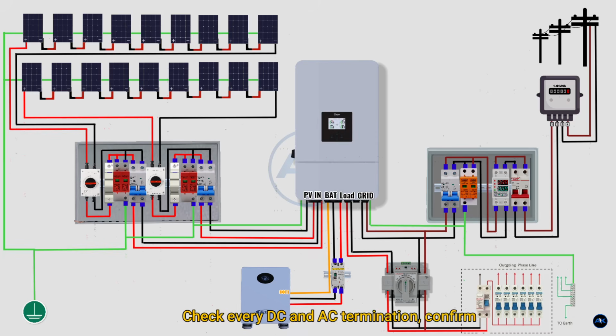Check every DC and AC termination, confirm torque settings, and ensure that all breakers, isolators, fuses, and surge protectors are correctly installed. Verify the polarity is correct on all DC circuits and that grounding is continuous across the panels, inverter, and battery. Next, ensure that all system breakers are in the off position.